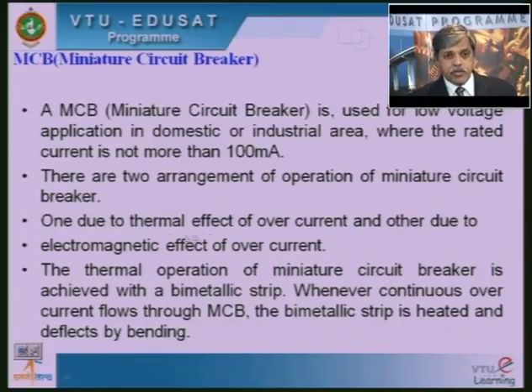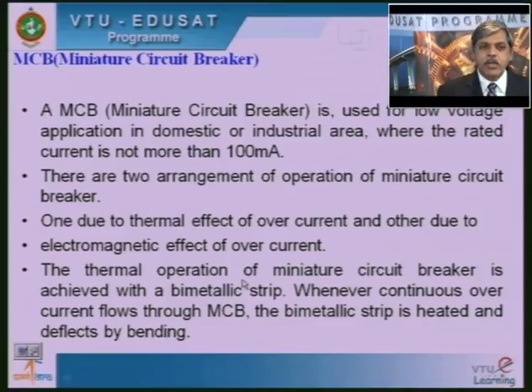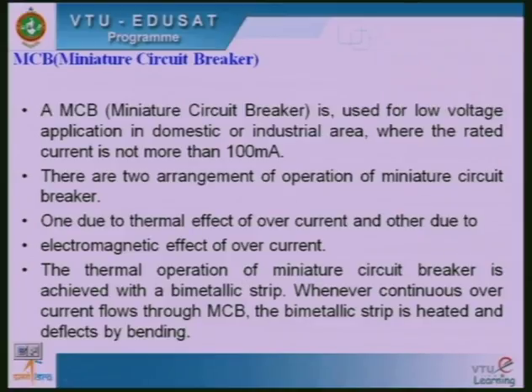So for the thermal operation, we have a bimetallic strip here. These bimetallic strips have a property of increasing their length when the temperature increases. So due to that there will be a gap. I can arrange the bimetallic strip in such a way that when there is an increase in the length, there can be an open circuit in the circuit breaker. Because of that open circuit, the circuit continuity will not be there, so the faulty system will be disconnected from the supply. That is how the bimetallic strip works, how the MCBs will work.